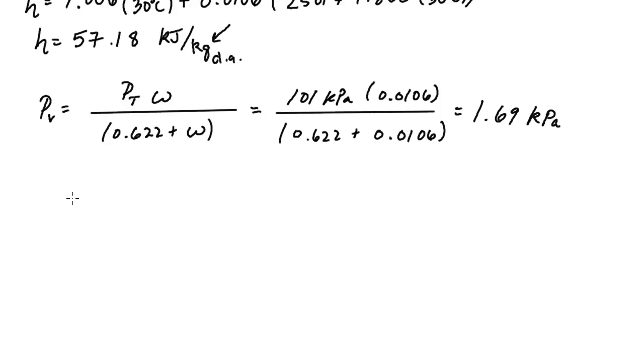And remember, usually when you think of natural logs and exponentials, they really shouldn't have units, but in this case they do. This is just a formula fit to data. The natural log of 1.69 is 0.523. E to the 0.523 will actually give you 1.69. So this would go in for all these alpha terms. This here is simply the 1.69. And if you do this calculation out, you will get a dew point temperature of around 14.86 degrees centigrade.